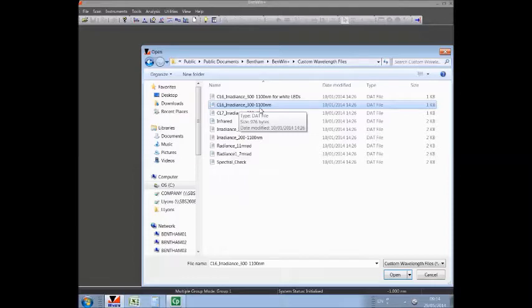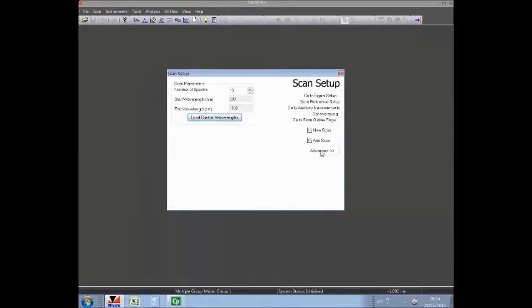In certain cases, for example with white LEDs where there's very little emission above 800 nanometers into the range of the low response silicon detector, it's desirable to increase the bandwidth to 10 nanometers or even more to try and increase the throughput and lower the noise equivalent irradiance. And it's for this reason that the CL6 300 to 1100 for white LEDs has been generated: 2 nanometers to 400, to 800 nanometers, 5 nanometer steps, and then 10 nanometers thereafter. For the moment we will select the CL6 300 to 1100 custom wavelength file.